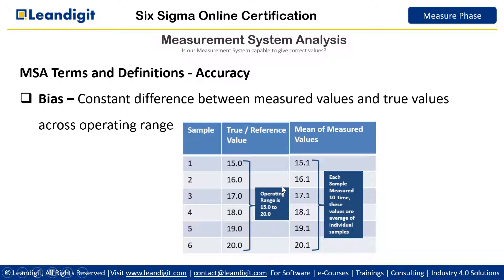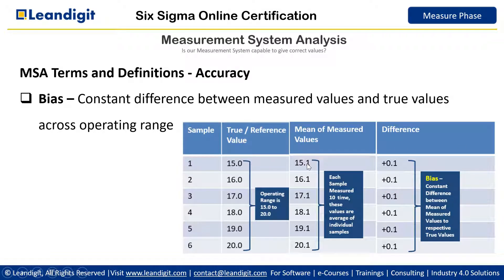Each sample is measured 10 times. We measured sample number 1 ten times using the instrument we want to calibrate, and the average value of those 10 readings is 15.1. When we measured the second sample, the average value of the 10 readings is also 16.1. We see the difference between the measured value and the true value is plus 0.1, constant — always plus 0.1. When there is a constant difference between the mean of the measured values and their respective true values, this is called bias.